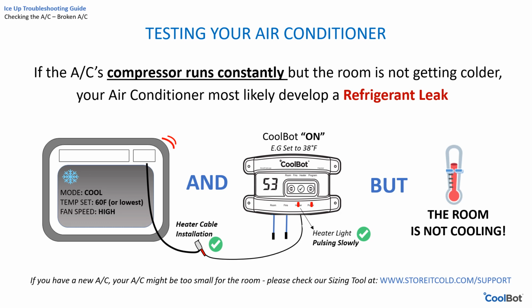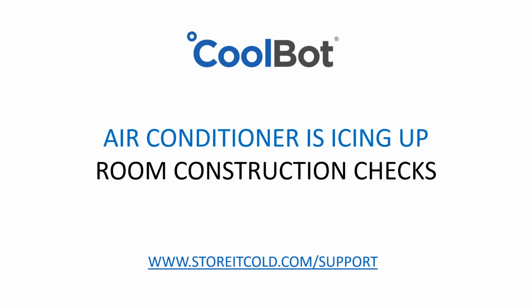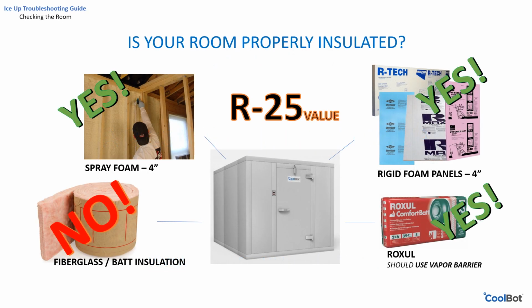If you haven't found the problem yet, this could be an issue with the room itself. Let's take a look at some of the common problems associated with the room construction. Is your room properly insulated according to our recommendations? We recommend insulating your room all the way around to an R value of at least R25 with rigid foam. Our preferred insulation is at least 4 inches of hard closed cell foam insulation, such as urethane, polystyrene, or polyisocyanurate. We do not recommend fiberglass batt or blown-in insulation.